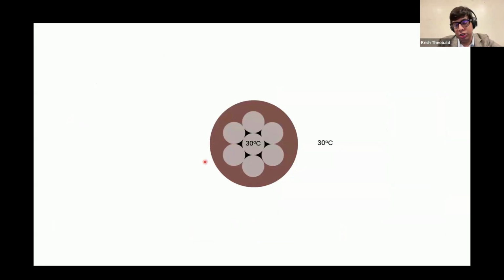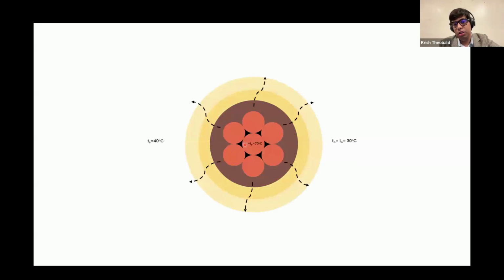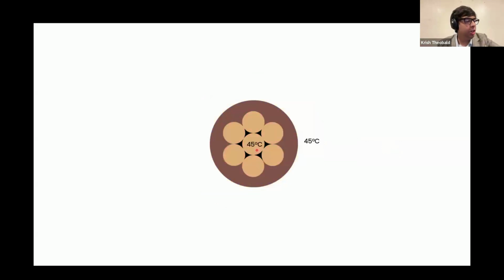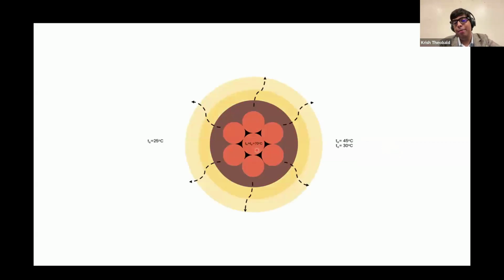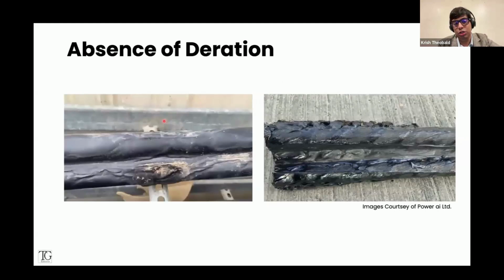So, ambient temperature. Like I said, assume we are at 30 degrees outside, 30 degrees inside, right? When you are running the cable at a maximum operating temperature of 70 degrees Celsius, with 30 degrees outside and 70 degrees inside, this is a 40-degree rise in temperature that the cable can handle. However, in most parts of the country, we see temperatures up to 45 degrees Celsius as ambient. What this means is that the cable can now only rise by 25 degrees. So earlier it was rising by 40 degrees, now it can only rise by 25 degrees. So obviously the current carrying capacity has to reduce.